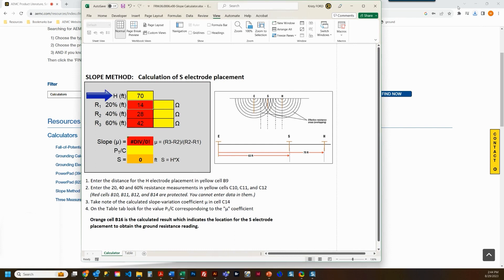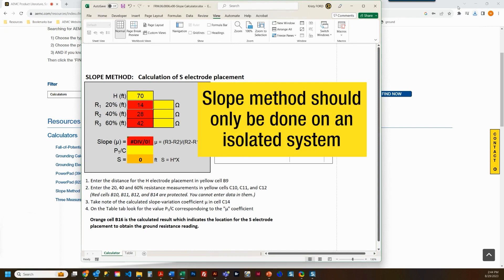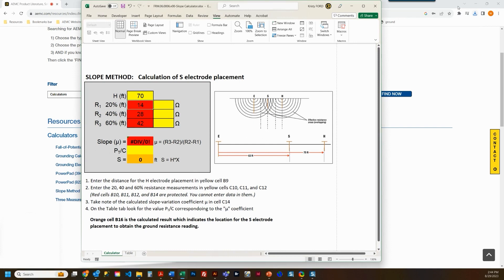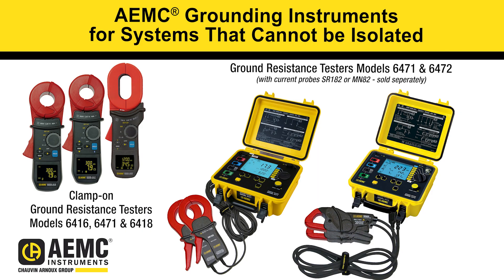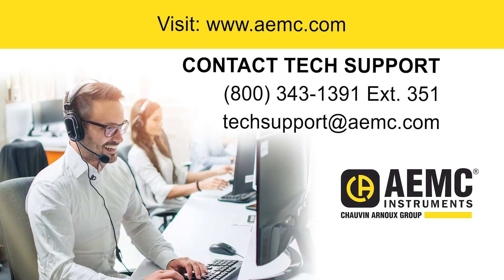Enter the distance to H to establish the three measurement positions. A quick note before proceeding: like fall of potential, the slope method should only be done on an isolated system. Other bonded electrodes, like those connected via utility neutral, will influence the measurement and invalidate the results. Be sure that you isolate your system before performing testing. AEMC also has testing instrument solutions for systems that can't be isolated — contact technical support or your nearby AEMC sales engineer or distributor for details.